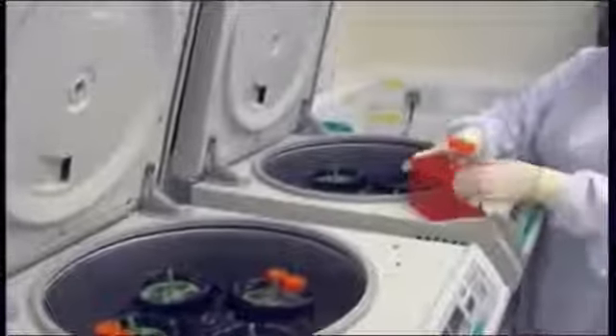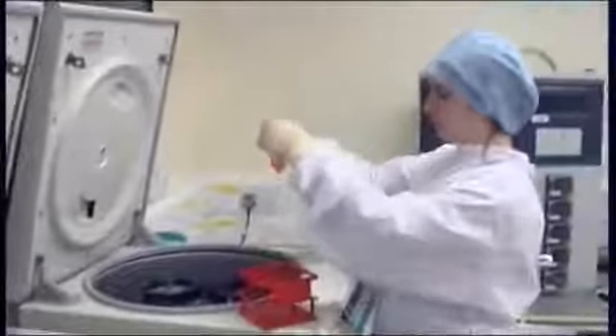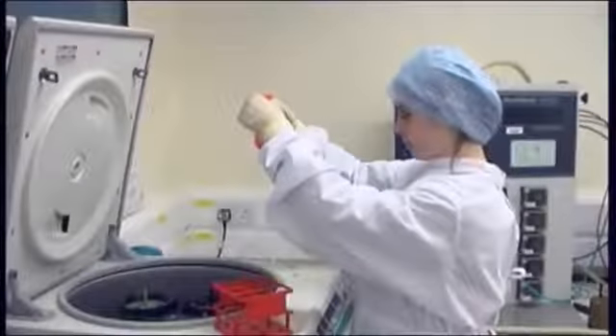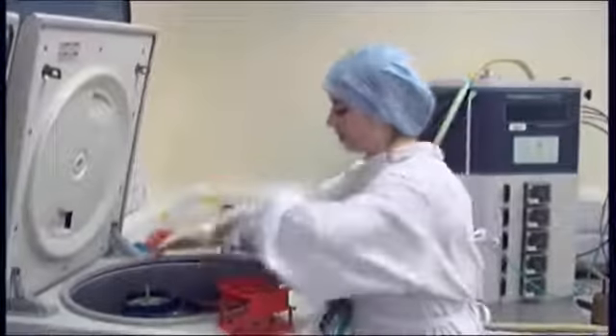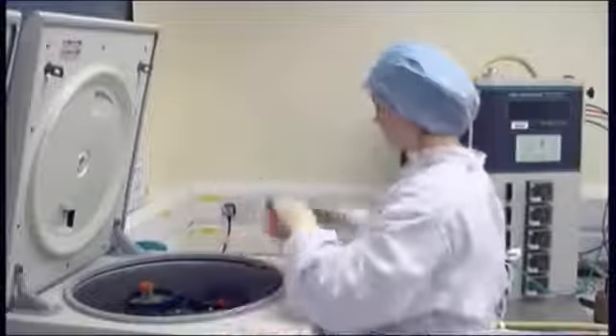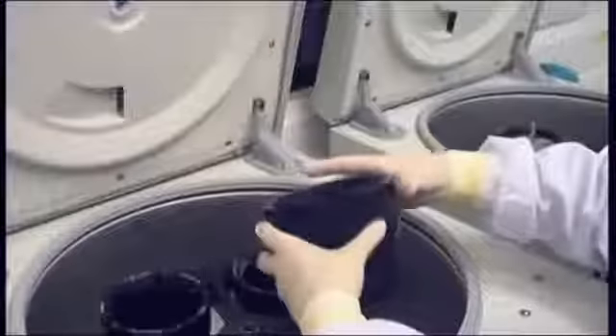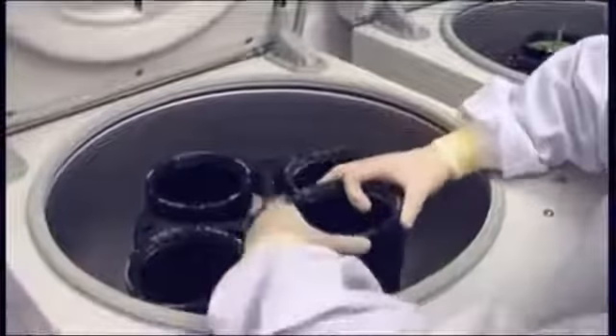During centrifugation, care should always be taken not to overfill the tubes and to balance them carefully to reduce the risk of damage to both the centrifuge and the cells, and reduce aerosol generation. Check regularly for any signs of corrosion. Cells sediment satisfactorily between 80 and 150 G. Higher gravitational forces may cause damage and promote agglutination of the cell pellet.